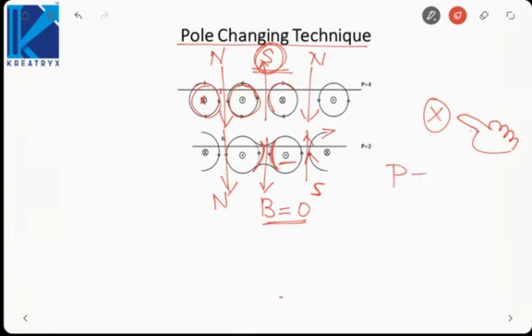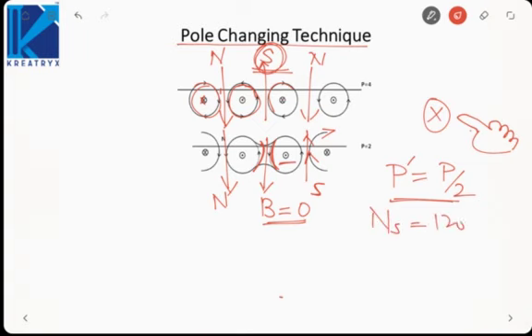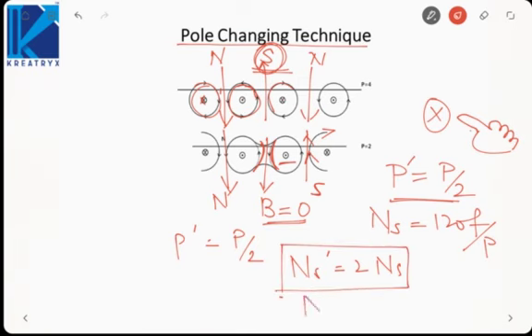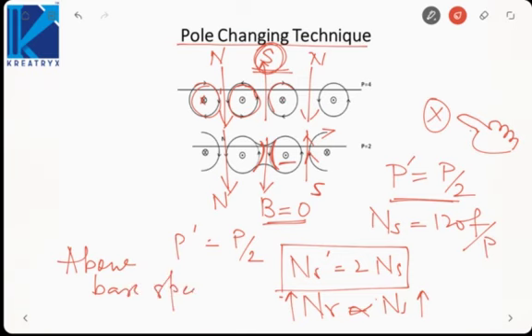To change poles, we reverse the current direction in one winding so both conductors carry current in the same direction. The fields cancel, net field is zero, and that pole is eliminated. By doing this we can reduce the number of poles to half the initial value. If poles become half, synchronous speed N_s = 120f/P doubles. With doubled synchronous speed, rotor speed also increases — this gives above base speed control.